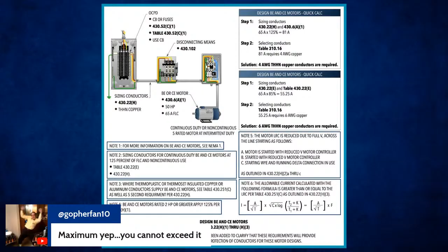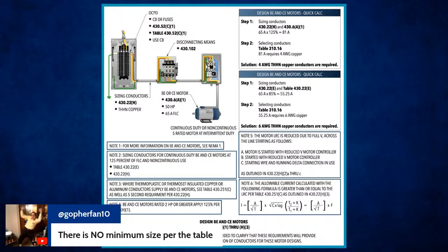Now I'm going to the maximum, and I'm looking at 430.52(C)(1) Exception 1(b), and it tells me I can take it at 400%. So 65 amps at 400% is going to give you 260 amps. You can't exceed that value. It says right there, I'll read it for you: the rating of an inverse time circuit breaker shall be permitted to be increased, but in no case exceed 400%. So in no case can it exceed. That means I have to do what? Drop down. If I come up with 260 amps, I go over and look at Table 240.6(A). The next size below that is 250 amps. But can I go below that 250 amps, maybe to a 200 amp, Jeremy? Sure I can.